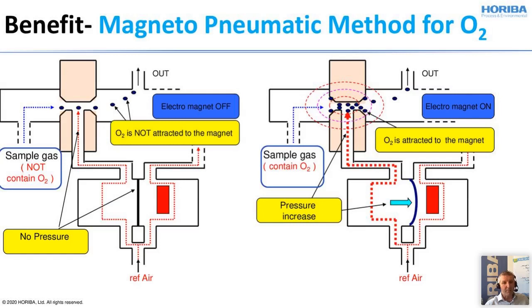HORIBA MPA, magnetopneumatic analyzers, uses air as the carrier gas. Hence, no cylinder gas as carrier gas is required. The magnetic field uses an AC-driven electromagnet, and the signal is processed as AC signals, contributing to stable measurement values.